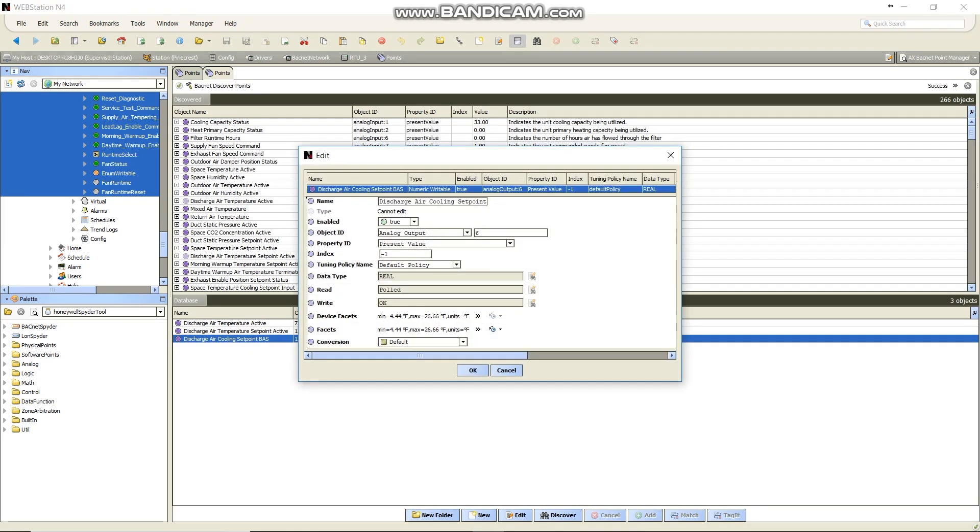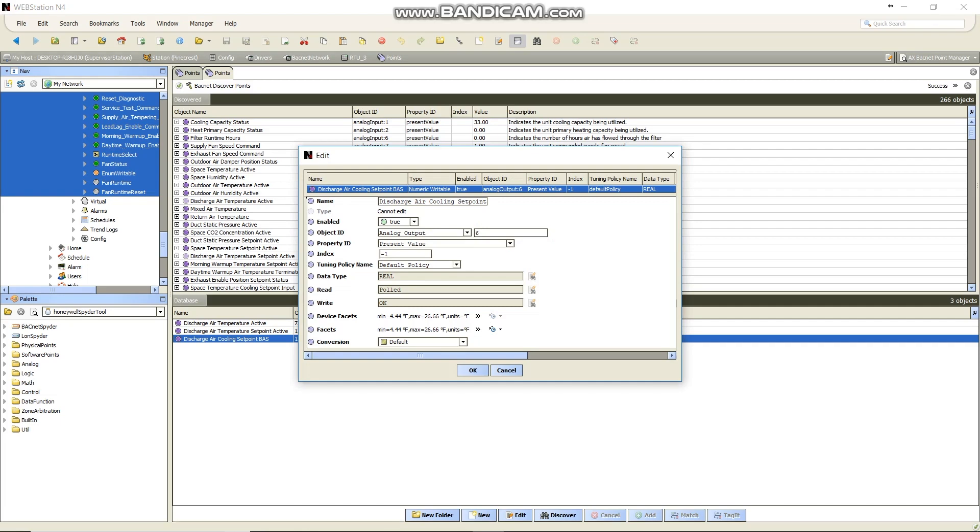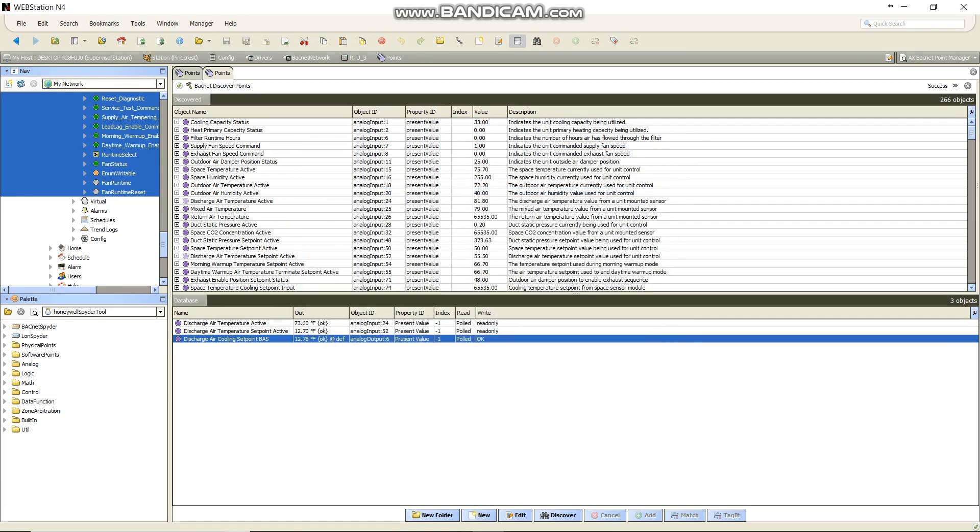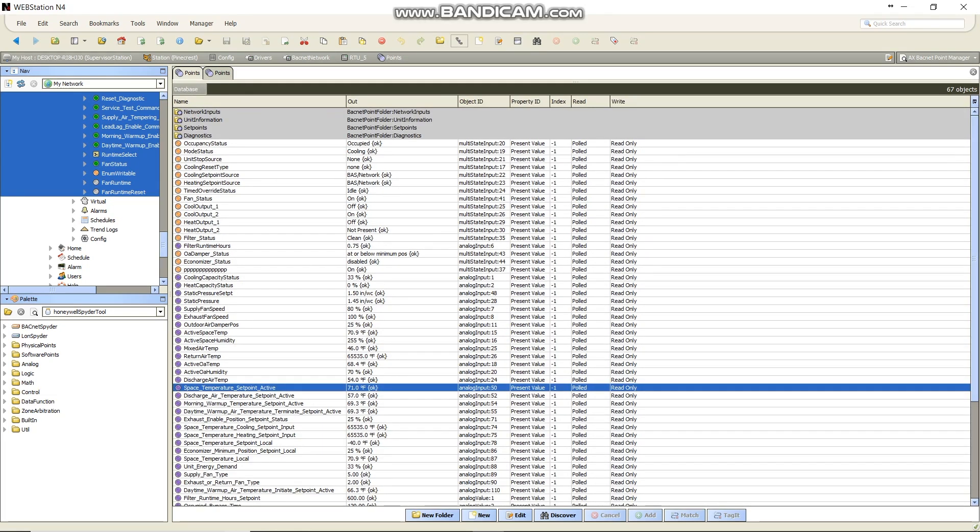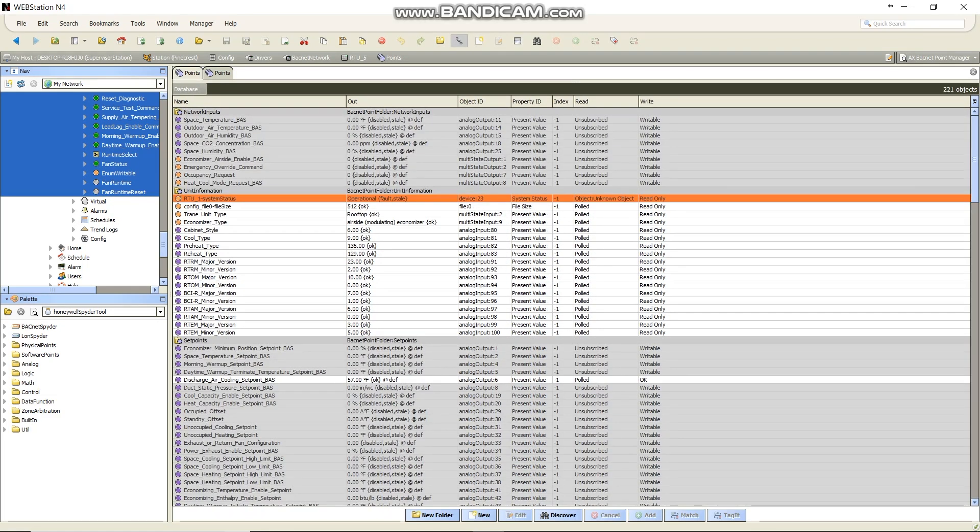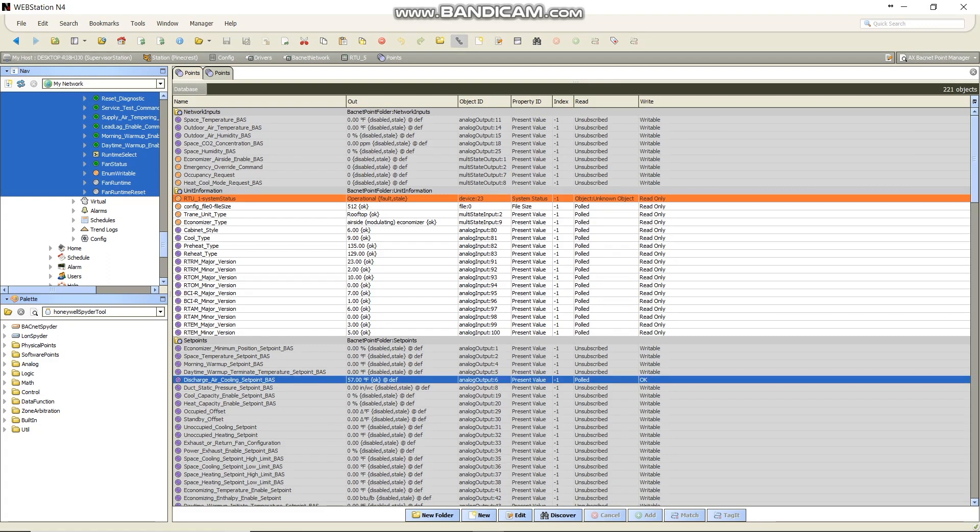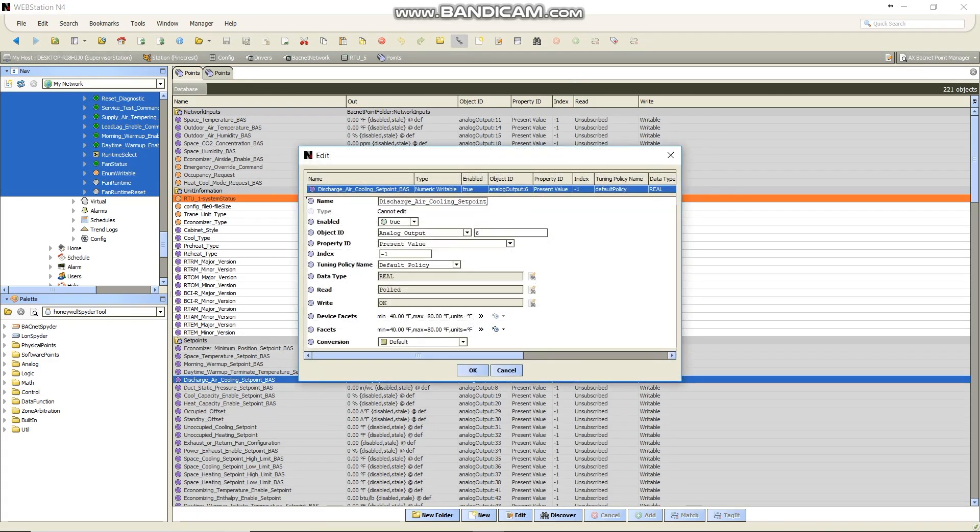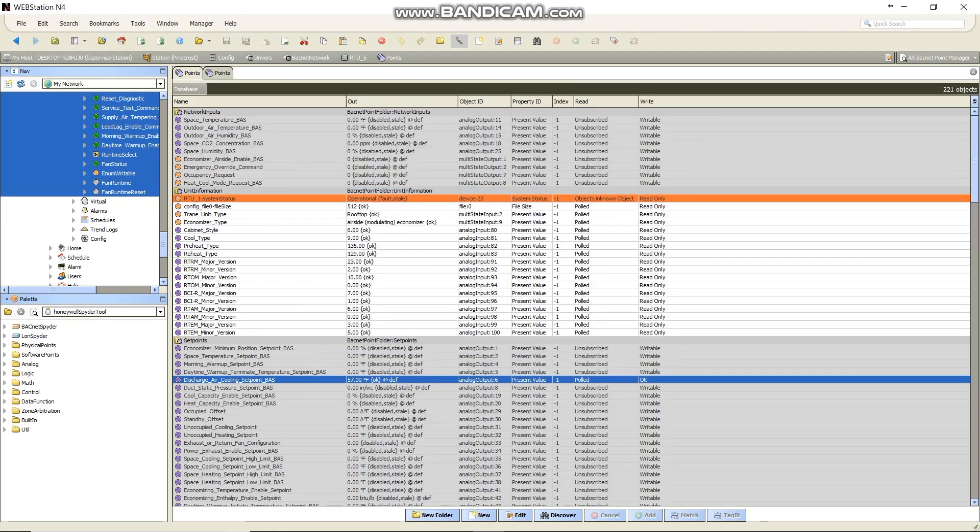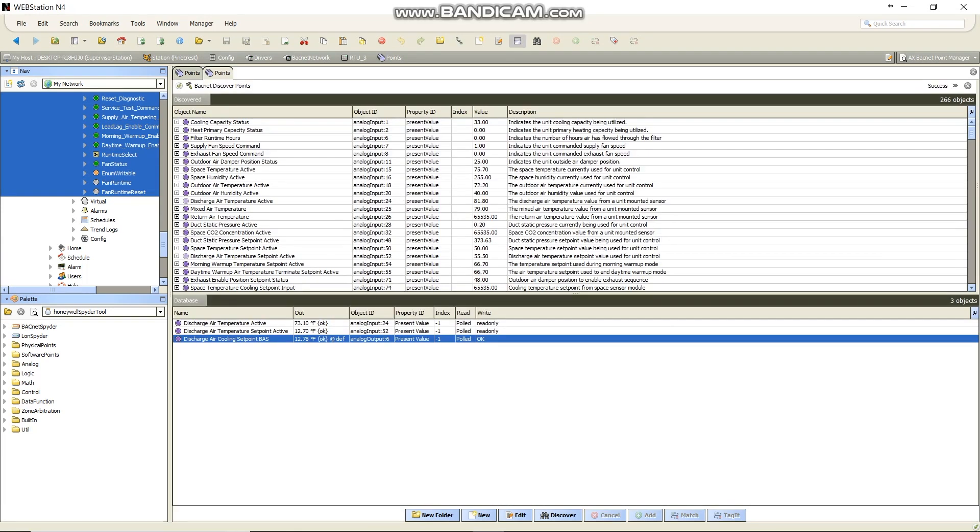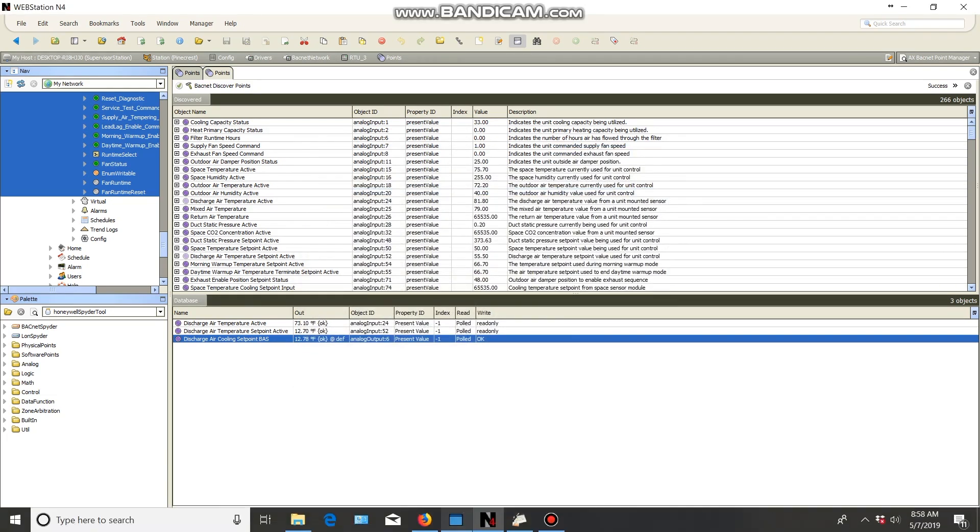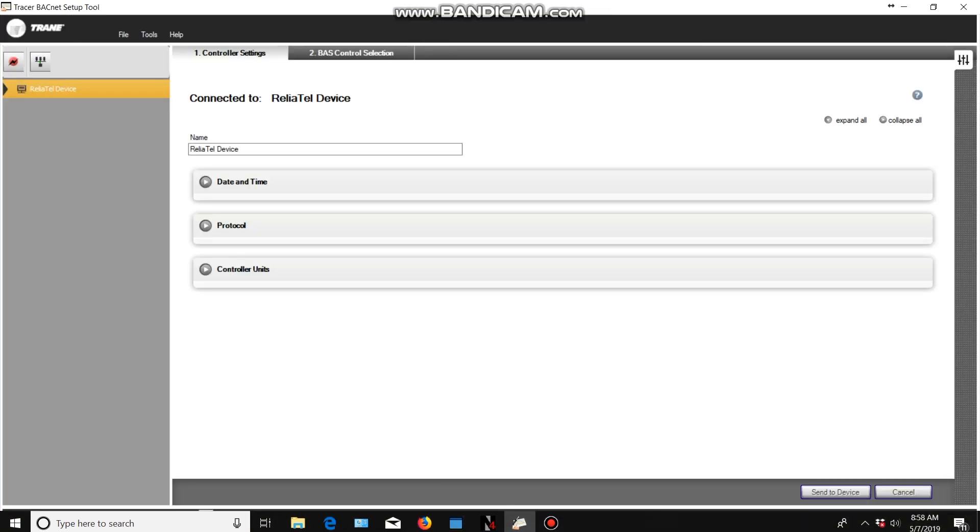And I don't know, 26 is too big of a number. But I can come back over here, and I can look at this. That's it. I was looking at the wrong point. So this is the discharge air cooling setpoint BAS. You saw those facets between basically 4 and 26. And then when I come over here, same point, discharge air cooling setpoint BAS, 40 and 80. So these are the same two devices, or same model controller on the same type of units, and I've got different device facets and ranges for the min-max.